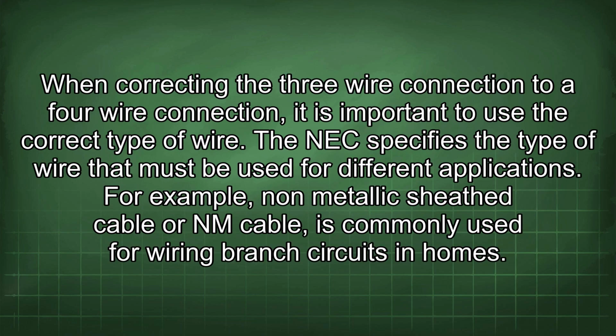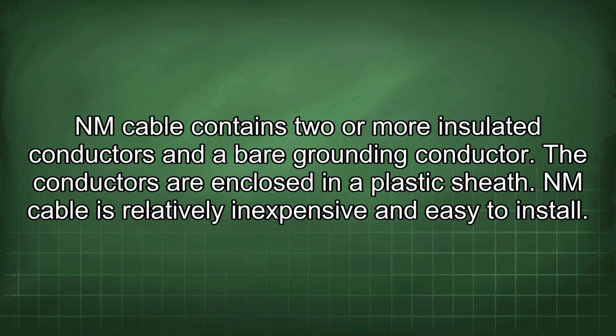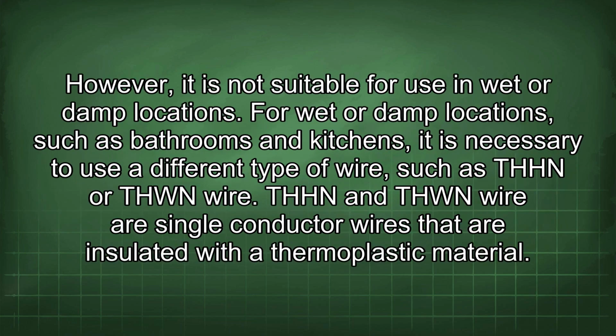When correcting the 3-wire connection to a 4-wire connection, it is important to use the correct type of wire. The NEC specifies the type of wire that must be used for different applications. For example, non-metallic sheath cable, or NM cable, is commonly used for wiring branch circuits in homes. NM cable contains 2 or more insulated conductors and a bare grounding conductor. The conductors are enclosed in a plastic sheath. NM cable is relatively inexpensive and easy to install. However, it is not suitable for use in wet or damp locations.